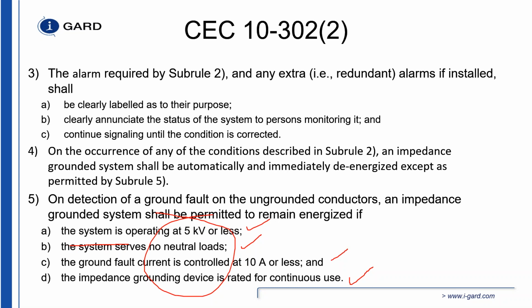Okay. Can the Sigma 3 relay successfully monitor health and continuity of the NGR circuit where a reactor is used, not a resistor? I've never tried it with the reactor because if we're injecting a frequency on the system, well, let me correct this. In passive mode, yes, we can monitor the integrity of the reactor in passive mode. Where we have an issue is in active mode.